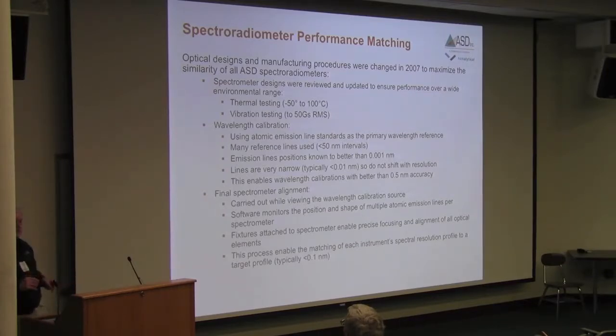But if you're trying to use multiple instruments for the same application, what you really don't want is every one as good as it can be. You want everything to be the same. So we put in place a program to have specifications both on the high and low side, and also a specification at many different wavelengths, so that the profile of the spectral resolution was very constant from machine to machine. And we also changed the ways we did wavelength calibration.